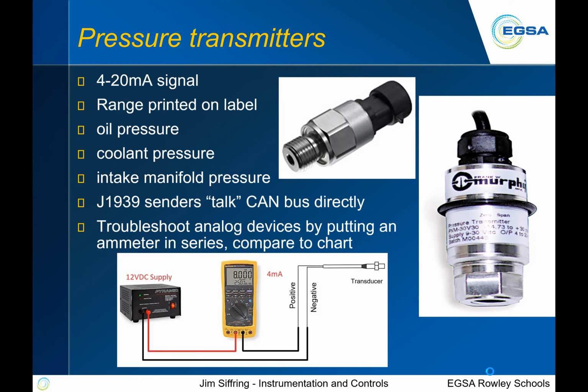Generally speaking, if we look at that lower graphic there, you see a 12-volt DC supply, you'll see your meter, and you'll see a transducer. We're running a current. They provide a voltage, which will give us a current that'll flow through that transducer, and that transducer will give us a proportional current reading out for whatever measurement it's taking there.